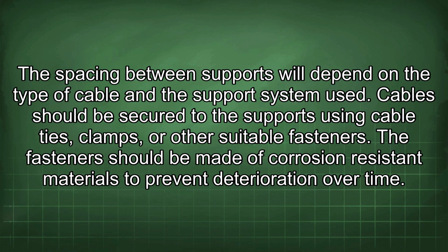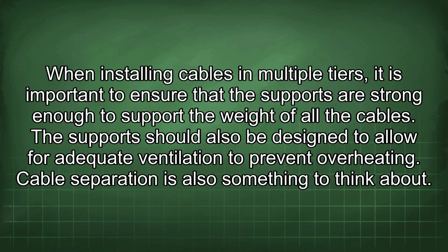Cables should be secured to the supports using cable ties, clamps, or other suitable fasteners. The fasteners should be made of corrosion-resistant materials to prevent deterioration over time. When installing cables in multiple tiers, it is important to ensure that the supports are strong enough to support the weight of all the cables. The support should also be designed to allow for adequate ventilation to prevent overheating.